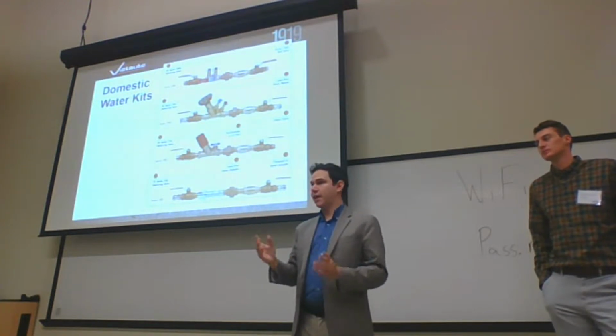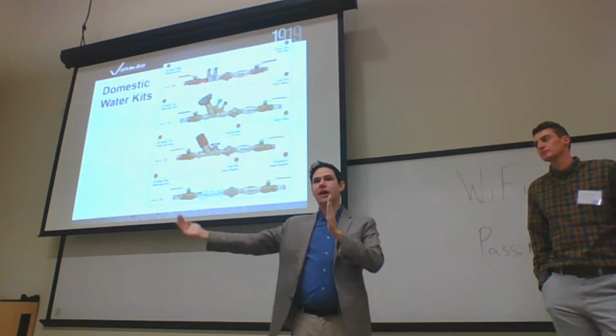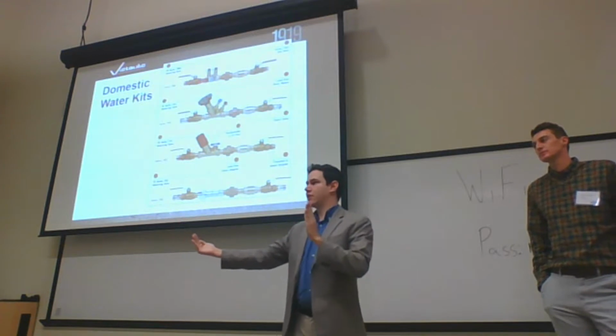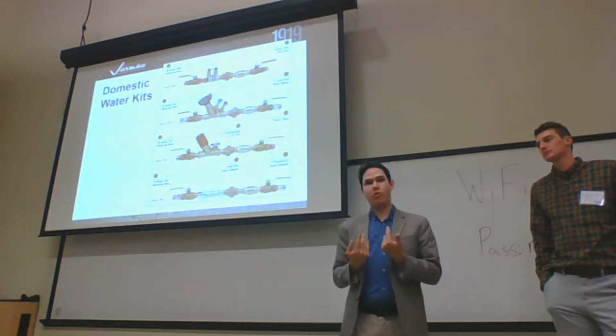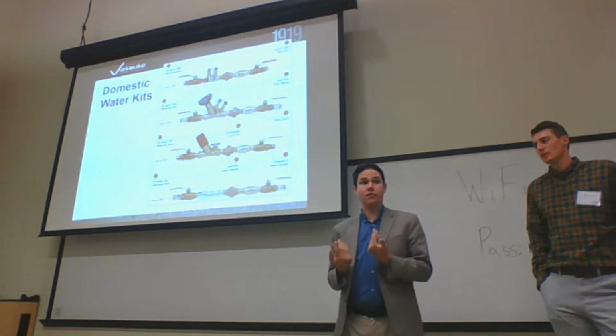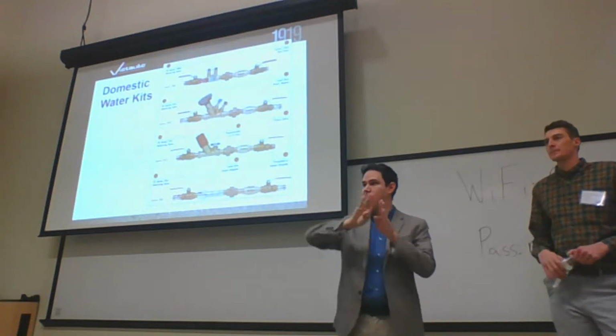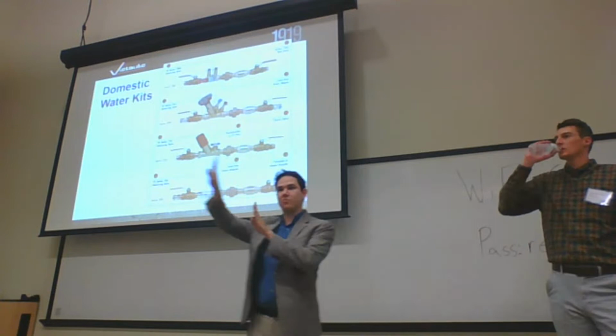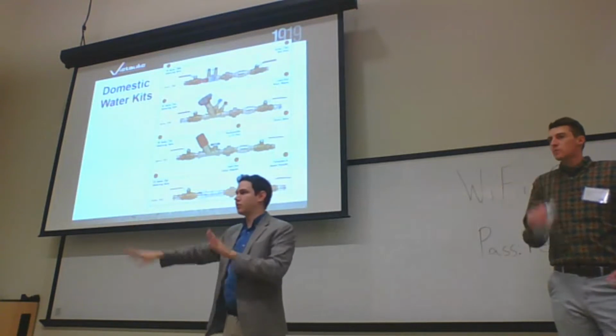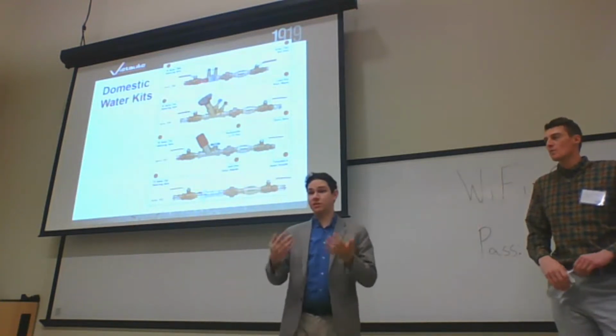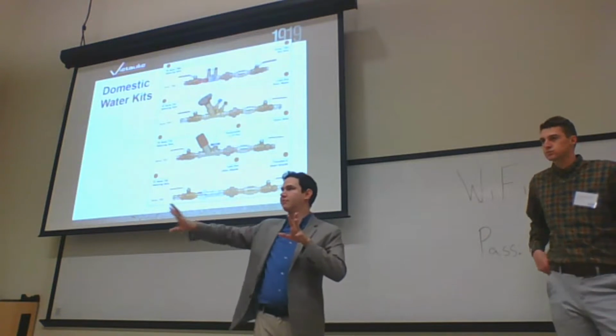that you want. And when you're thinking about that in a cascade effect, many branches, many risers, the ones closer to the pump and boiler are going to get hot quicker. So this one will close down and push the water further and keep pushing the water further, and all of the branches will get the right temperature. So it's important to think in this cascade effect.